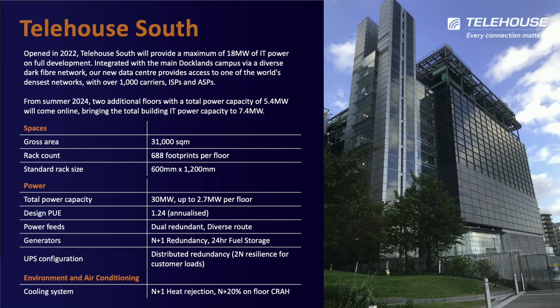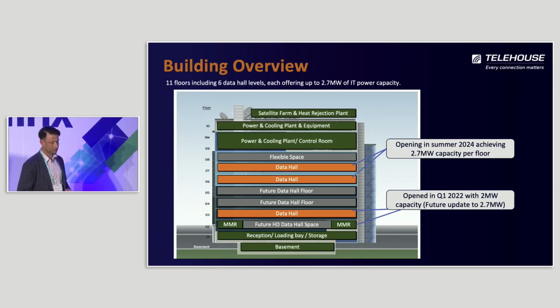Dual redundant, diverse fibre-routed feeds, coming at the moment from Blackwall Way. In the future, we'll be feeding ourselves from our own Telehouse-owned 132 substation on the Docklands campus. N+1 redundancy on generators with 24-hour fuel storage, and distributed redundancy of 2N to the customer rack across 2 data hall floors. And then N+1 heat rejection on the roof with N+20% on-floor CRAH units.